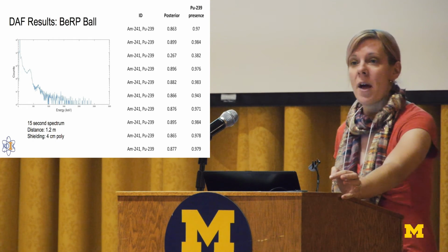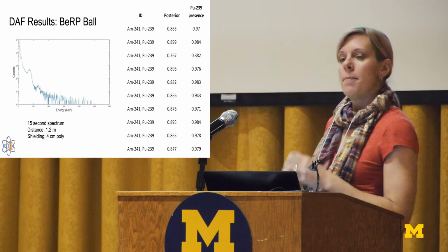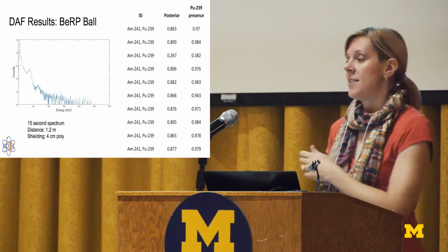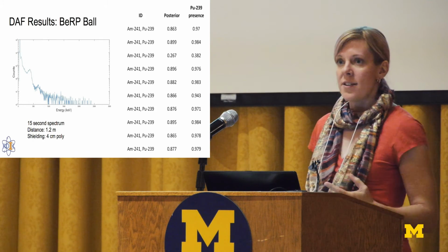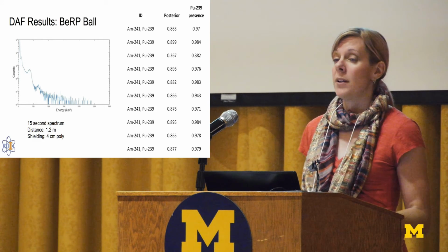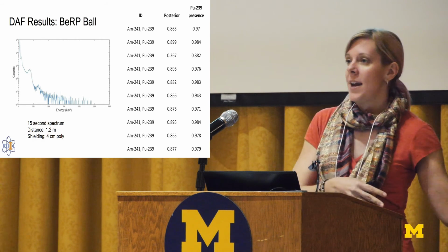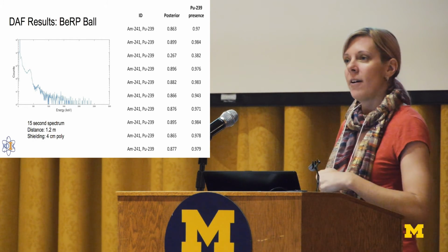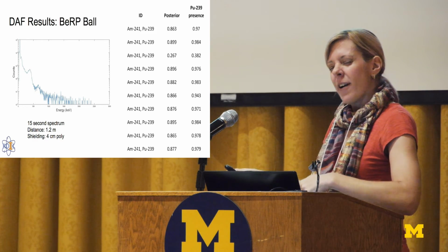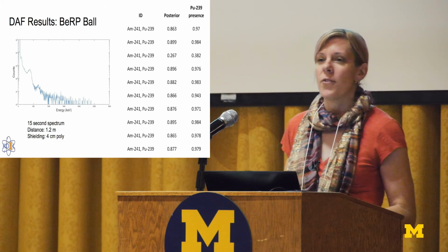Now, I have 3 columns here. The first column is of all of the models in our library. And right now, our library is based on the ANSI standard for handheld isotope identifiers, plus several more isotopes that are of use to us. So it's a pretty complete library. And then we come up with up to 3 combinations of each isotope. So every isotope in the library can be combined with every other isotope and then another isotope. Okay, so that's as far out as we go right now. We could add 4 or 5 or however many.